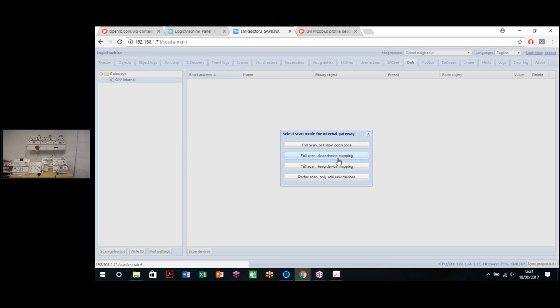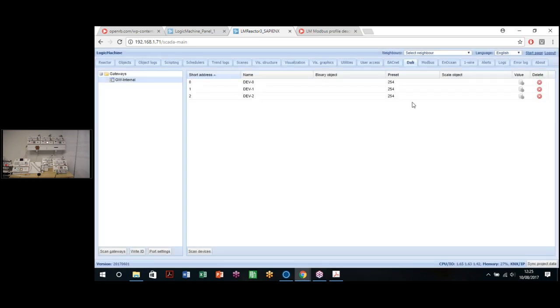We can scan and clear the device mapping that we have already made. We can also make a full scan, keeping the mapping that we have created with other objects, and just find the devices and do not touch anything on the logic machine. In this case, let's make a full scan, setting the short addresses. And it should show that we have three ballasts. Even though we have one, it will show us the three channels of the one ballast that we have. This is a RGB ballast, so it has three different channels that we can control independently.